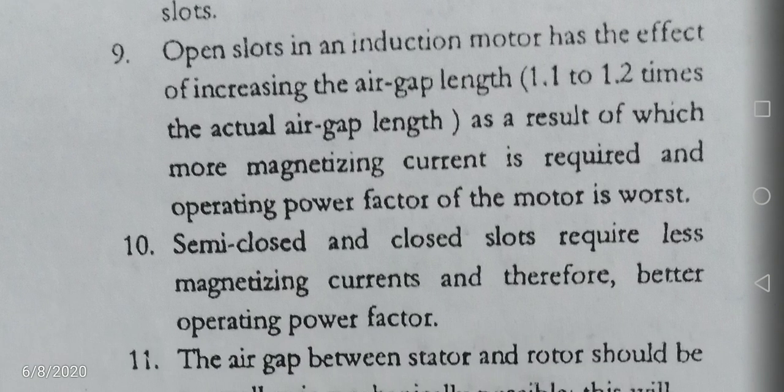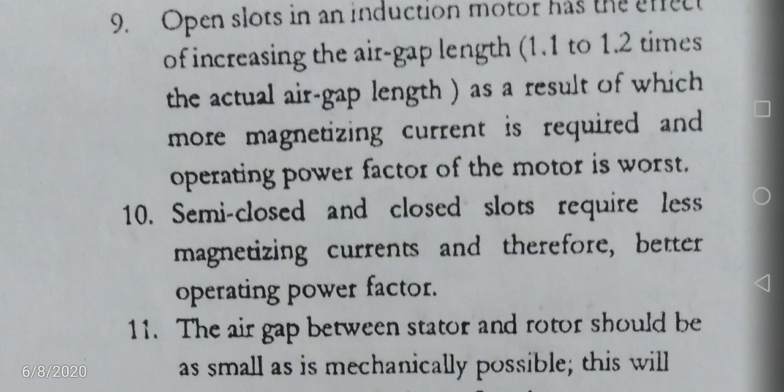Semi-closed and closed slots require less magnetizing current and therefore give a better operating power factor. So semi-closed and closed slots are better suited for higher power factors. But in semi-closed and closed slots, the torque is less.